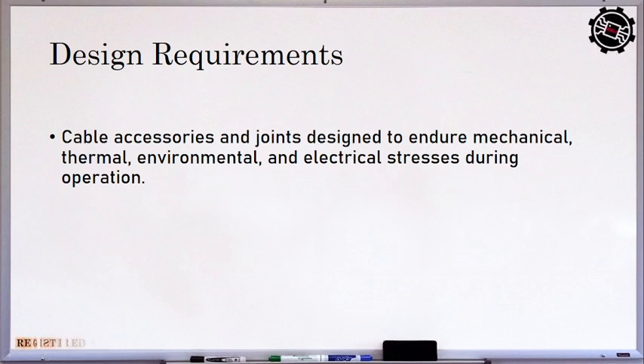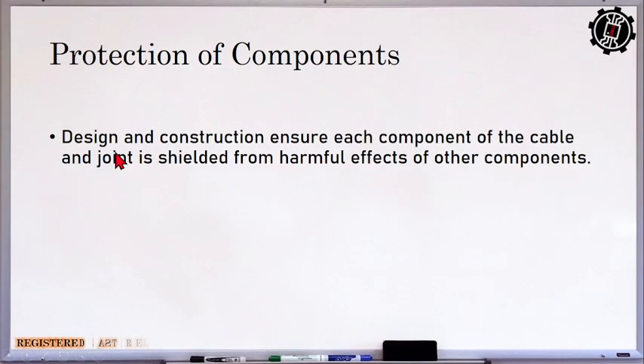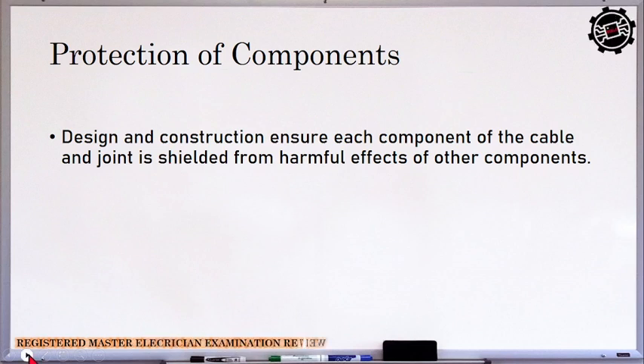Okay, so design requirements. For the cable accessories and joints, they must be able to endure mechanical, thermal, environmental, and electrical stress during operation. So protection of the components of our cable system or the supply system. The design and the construction should ensure each component of the cable and joint is shielded, so itong term, naka-shield siya from harmful effects of other components.